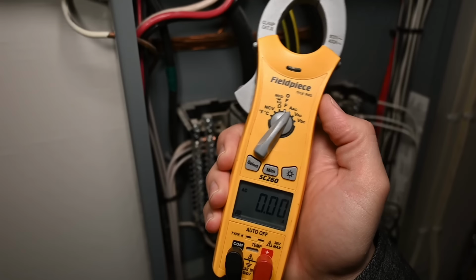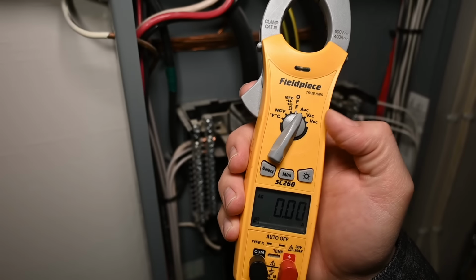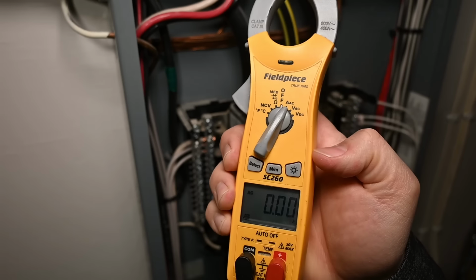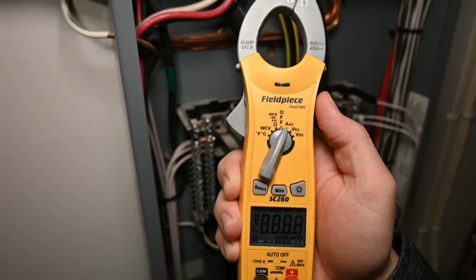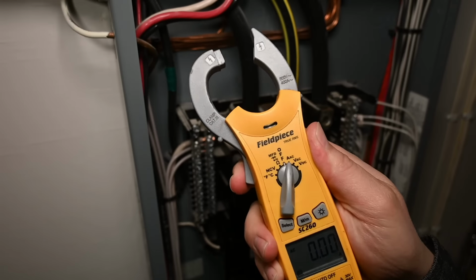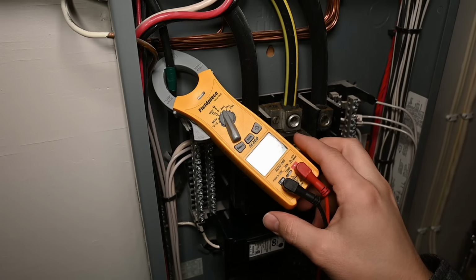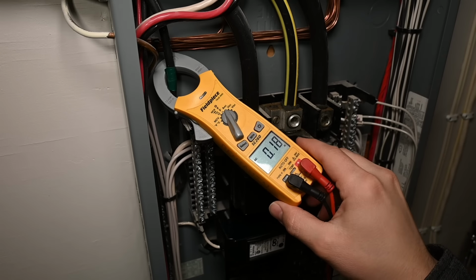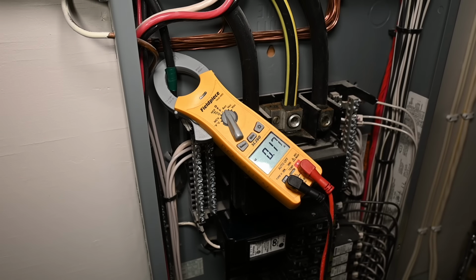Thank you to whoever pointed out that this is not an amp meter, this is an ammeter when you're using it in the amp measurement mode. So we're going to put that into our ammeter mode, and then we're going to clamp it around our EGC going out to the panel outside, and we'll see how much current is currently being carried. And you can see right there we're at like 0.17 amps. Earlier when I checked it, it was at like 0.22, so it's obvious that there is some difference depending on what is running at any given moment.